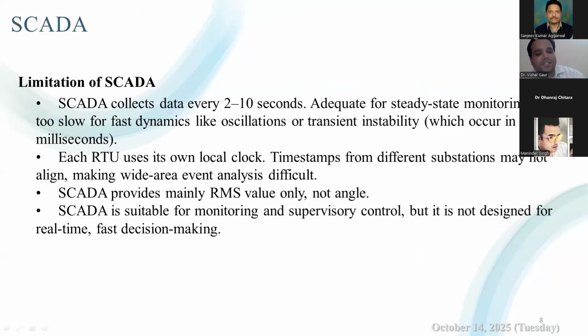Now, while SCADA has been extremely useful, it also has some serious limitations. The first one is that the data update rate is very slow, in this case 2 to 10 seconds. That is fine for steady state monitoring, but far too slow for fast dynamic events like oscillations or transient instability, which happen in milliseconds. Second, SCADA does not have global time synchronization. It relies on local clocks. Each RTU has its own local clock, so when events occur at different stations, their timestamps may mismatch. This makes it difficult to analyze wide area events accurately, because any small drift in the local clock may give the wrong analysis.